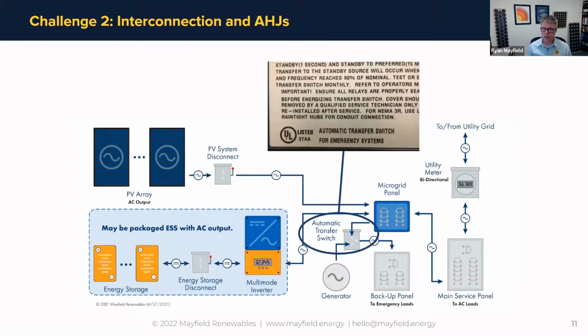In this very specific case, we would have loved for the generator to kick on, serve the emergency loads, the backup loads, and at the same time have enough capacity to charge the batteries. If we could have made it work, that would have been a better situation. The generator would have run at a higher efficiency value, and would have been able to cycle on and off and save even more fuel, which was one of our big goals on this project.